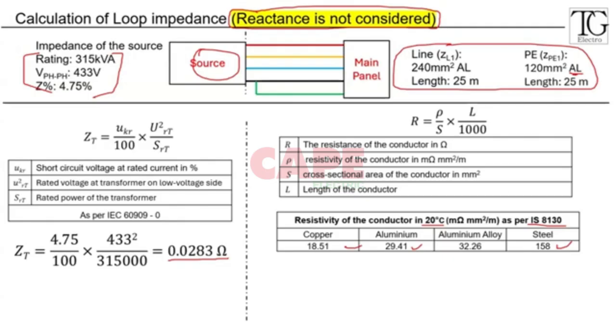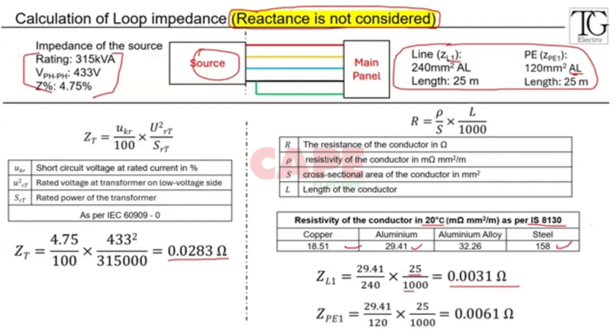I'm considering 20 degrees here. I don't want to complicate the process much, because Krish has done a webinar on the temperature and on the other factors, so I'm not going to talk about the correction factors. I'm going to talk only about a general scenario. Now you have these values. When you substitute the values for ZL1, aluminum is 29 divided by 240, into 25 meters, by 1000, and you'll get this value. And for ZPE1, if you substitute the same thing, you'll get this value.